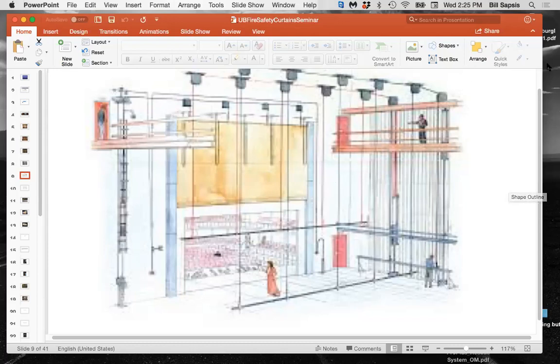So, I wanted to bring up the smoke doors early on, because I'm not going to go back to them. You need to know that they exist in your theater. And typically, if the theater was built within the last 30 or 35 years, their typical trip mechanism is a fusible link for an automatic trip. They also have pull stations, but let's talk about the fusible links first. They're up in the ceiling, up inside the door mechanism, and the ones they typically use are designed to separate. It's just two pieces of metal connected with some solder, and it burns through, it separates at approximately 160 degrees Fahrenheit. So once the fusible link separates, the doors fly open, and you now have air getting out of the building.